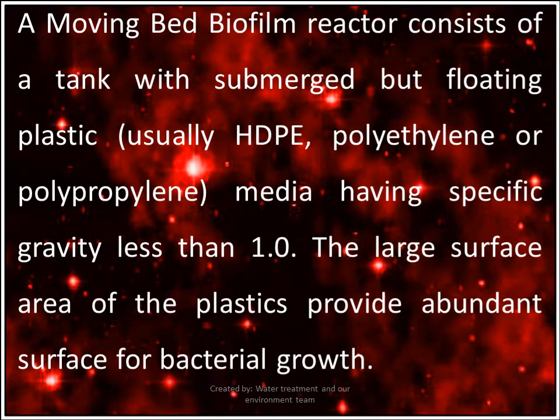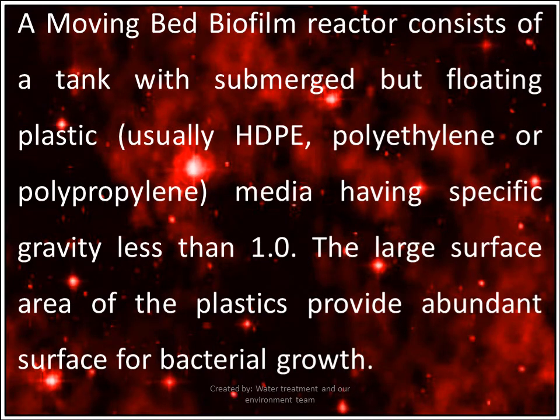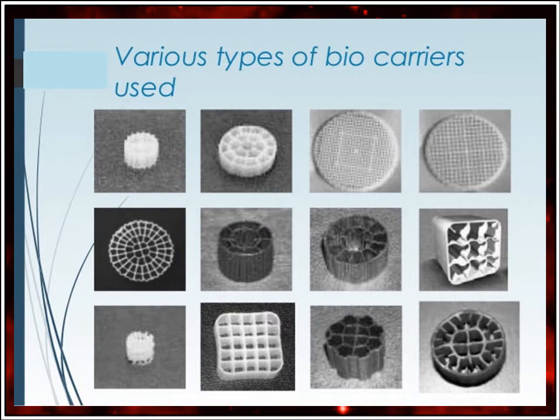A moving bed biofilm reactor consists of a tank with submerged but floating plastic media having a specific gravity less than 1, as seen earlier in the schematic diagram. The large surface area of the plastic provides abundant surface for bacterial growth. These are images of various types of biocarrier used in MBBR tanks. Because of these structures, the biofilm attaches and provides higher surface area in a lower space.